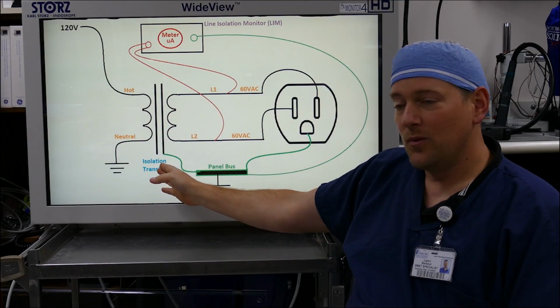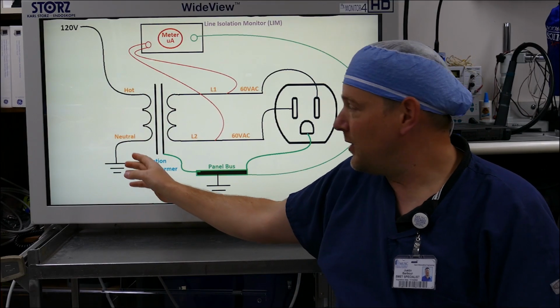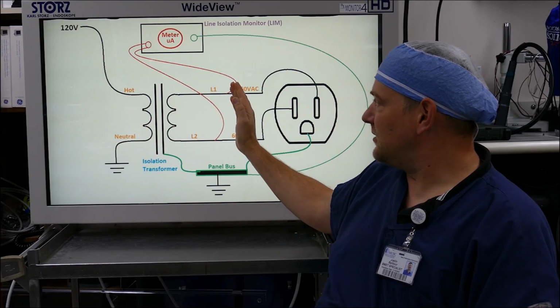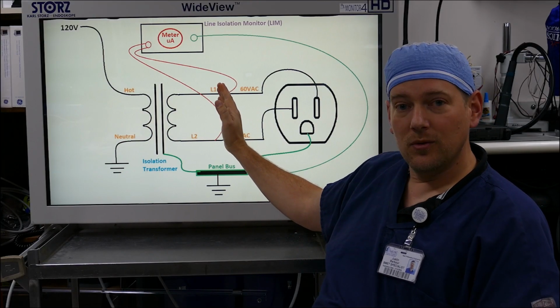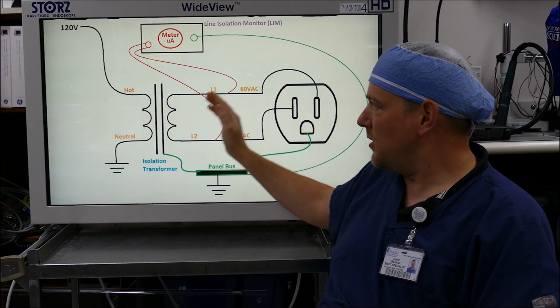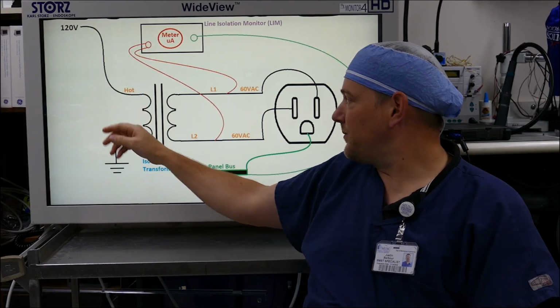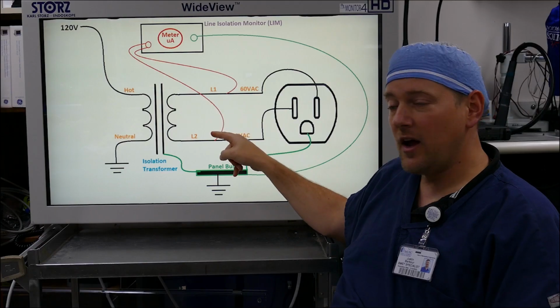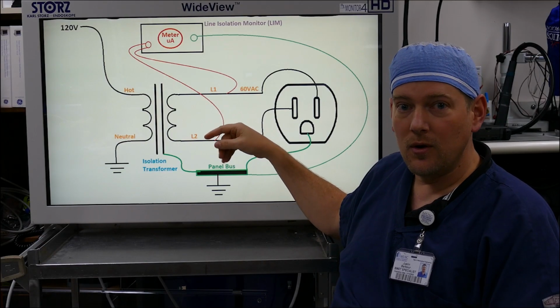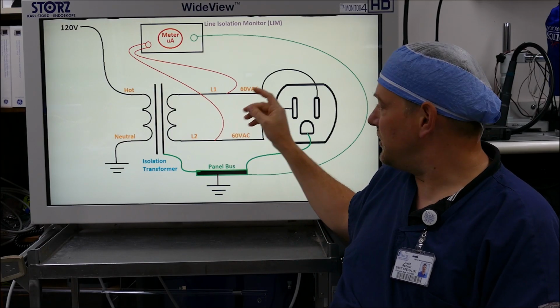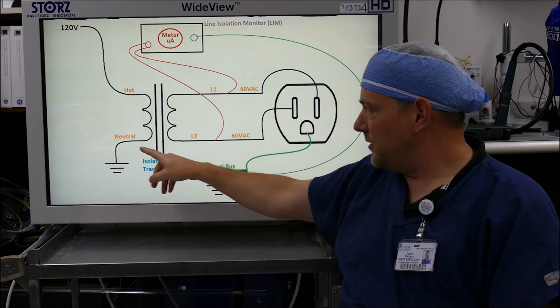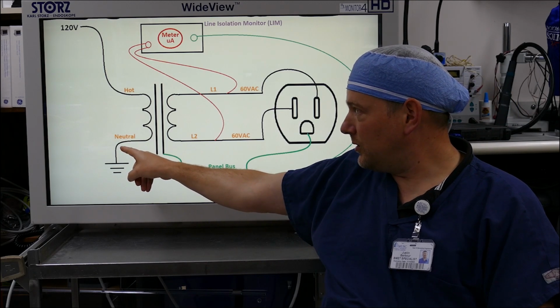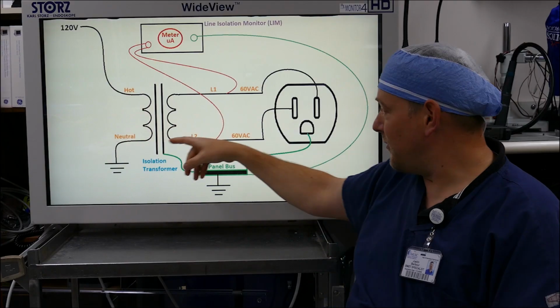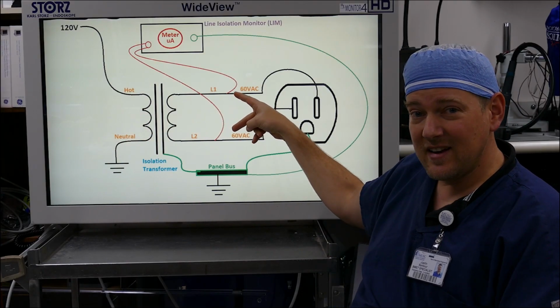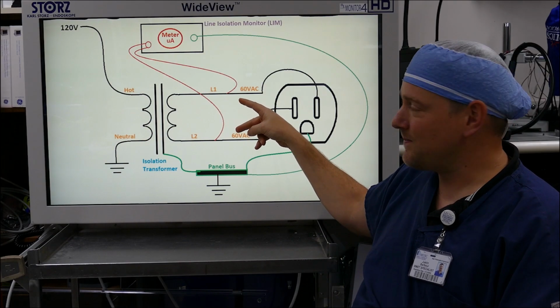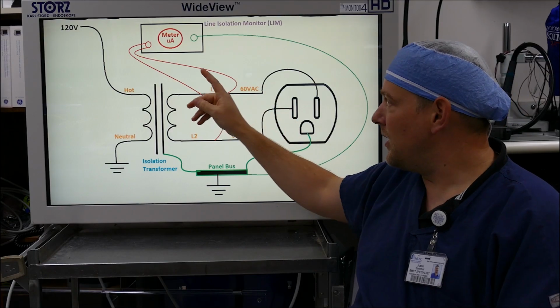You can see here, you have the isolation transformer, which separates L1, L2, which is inside the operating room, from the line power. So when you touch L1 or L2 through a cut cord or whatever else it may be, you are not part of the puzzle. Normally you are part of neutral, and when you touch hot, you get zapped. Over here, unless you touch L1 and L2, you will not get zapped. So let's walk through the flow.